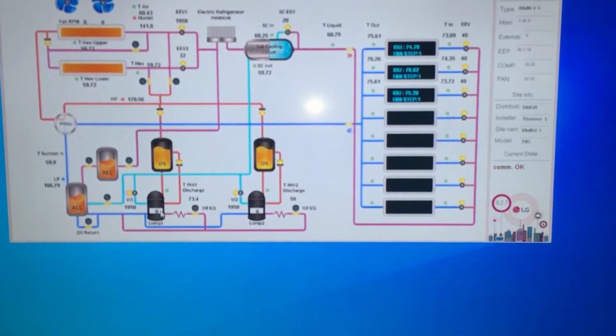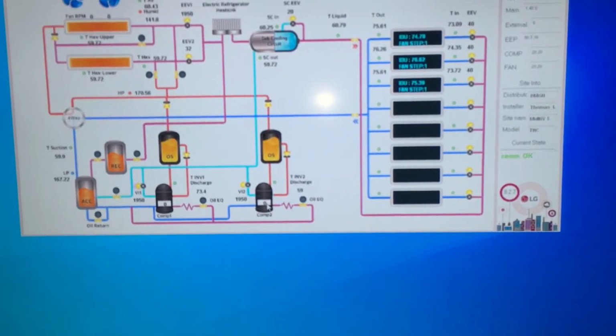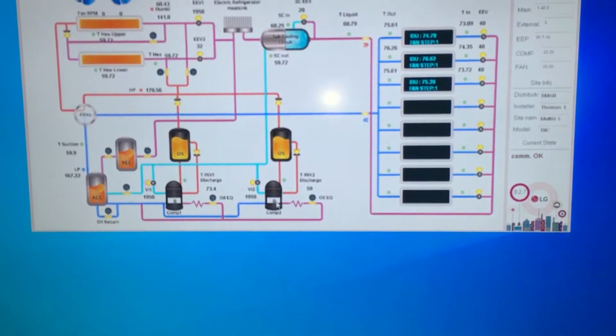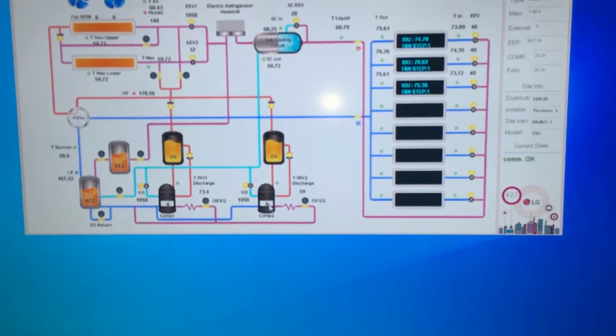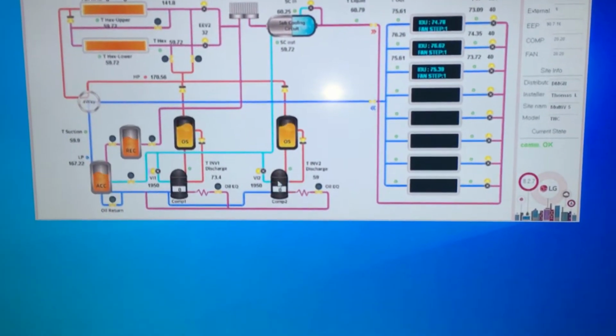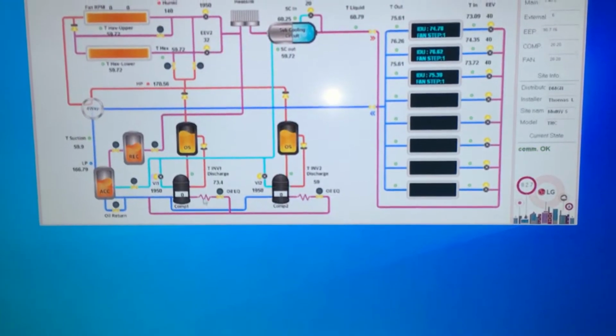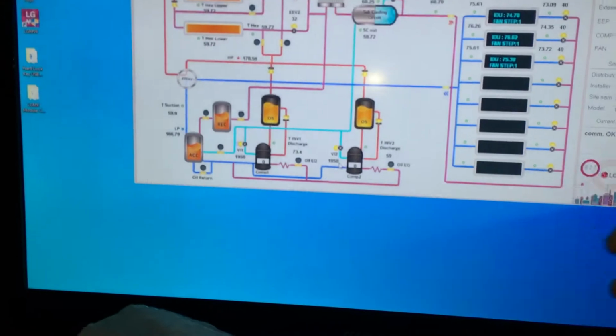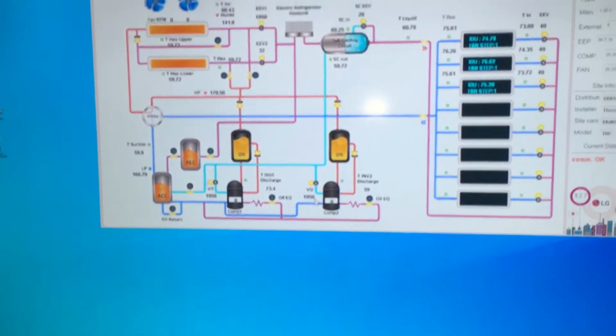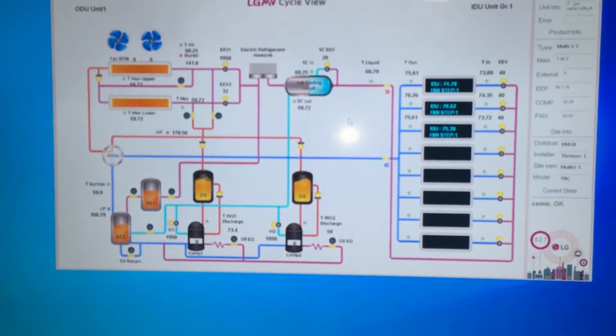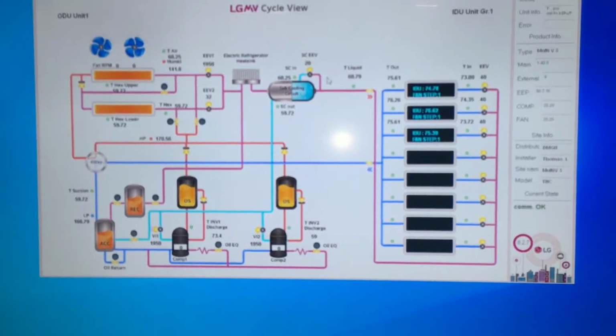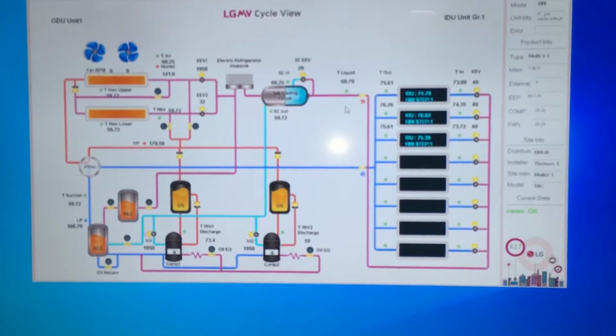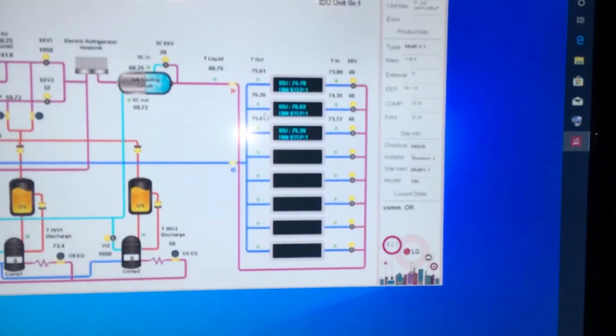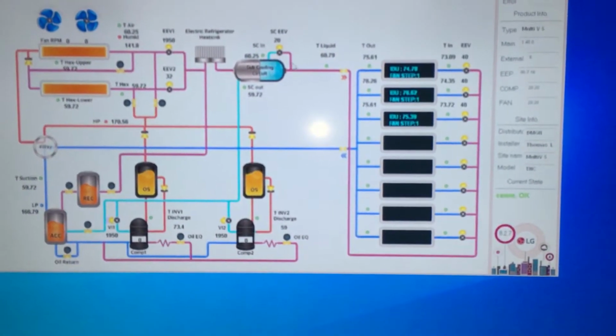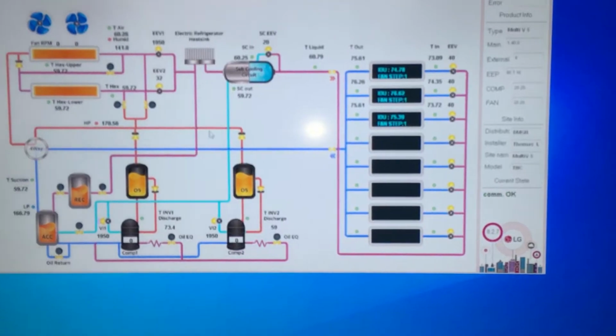You get to see when your compressors come on. Right now it's a really low load. Some of the lights, the heat load inside the system is turned down, so this particular one system is not actually operating. Probably if I had the other one over there turned on, those compressors might be operating at a very low level because it's so cold outside right now, and some of the lights are turned down inside, so the heat load in the room, you can actually see, okay, everything from the superheat, the subcooling.